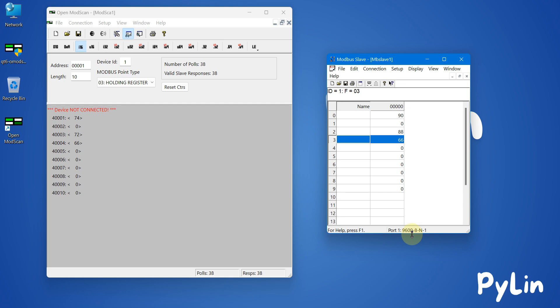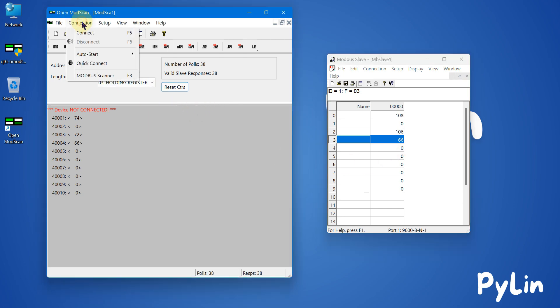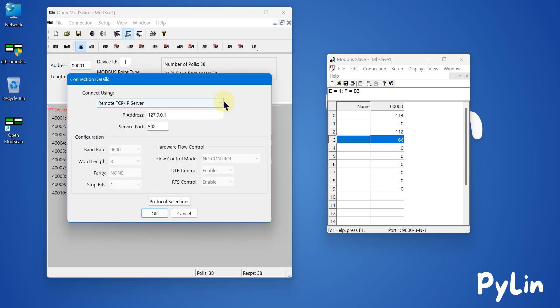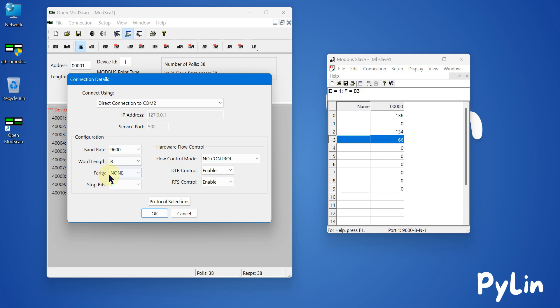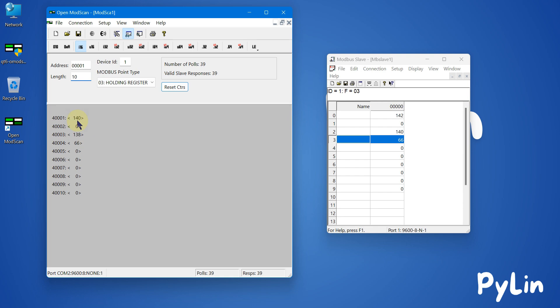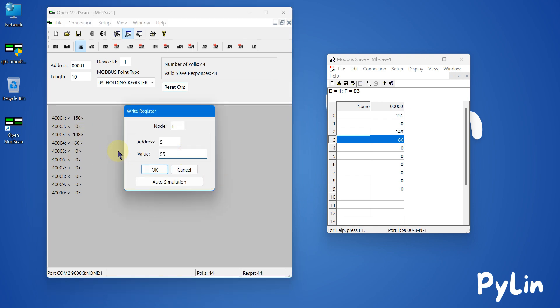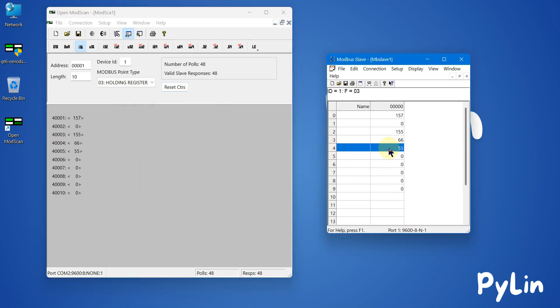To connect OpenModScan with this Modbus serial device, I go to Connection and click Connect. I select COM2 because COM1 and COM2 are internally connected, and specify baud rate 9600, data bits 8, parity none, stop bit 1. I press OK and you can see we have the data. I can also update a value — enter 55 — and you can see 55 is now available.